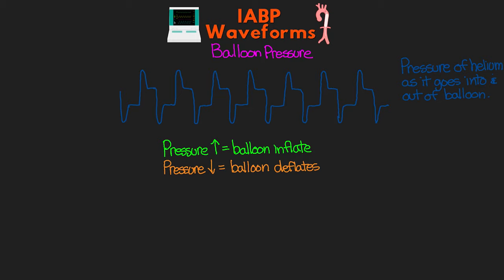The basic cycle for the balloon goes like this: the helium pressure increases — shown by the increase in the waveform — causing the balloon to inflate. Once the proper volume of helium is given, you'll see the pressure equalize, which is a little drop from the max pressure. Then the balloon pump keeps the balloon inflated, which is the plateau we see. Then at the right time, the balloon deflates — that's the next drop off — which occurs right before the next heartbeat. The proper balloon pressure waveform should really resemble a chair. I think of it as resting the heart, so we want a nice chair to rest on.